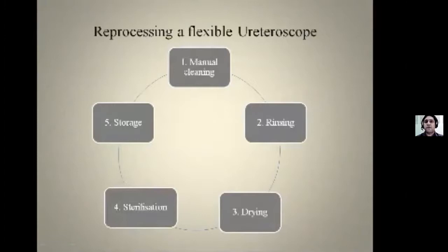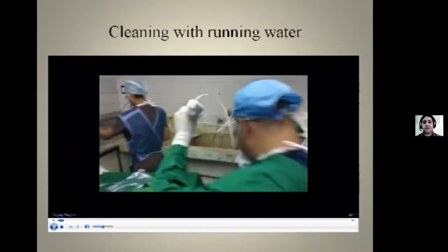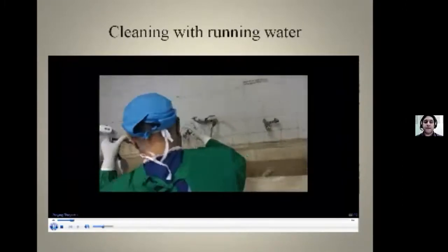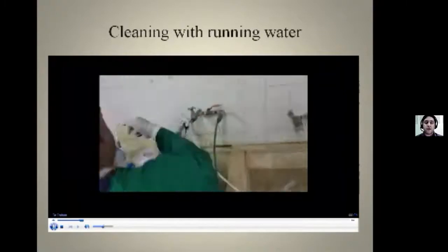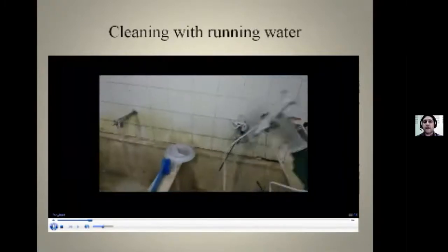Reprocessing of the flexible ureteroscope is first manual cleaning, then we rinse it, then we dry it, sterilize it, and then we store it. In the next few slides, I'll give an idea about this cycle. First, cleaning with running water. As soon as the case is completed, we have to remove all the debris and soiling on the ureteroscope with the help of running tap water.